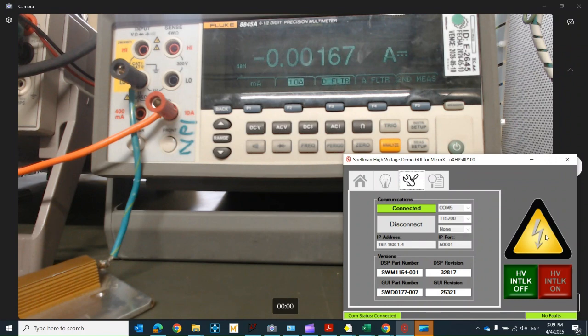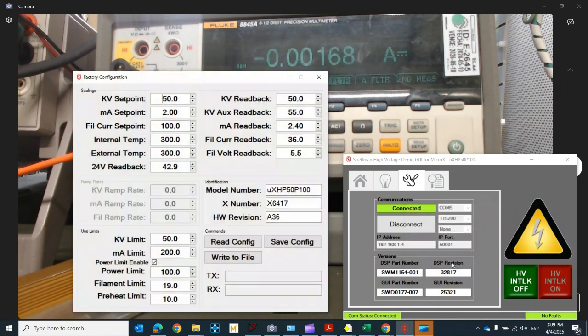Before proceeding with the computer interface test, we will also present a reminder of the access to the factory settings, which can be accessed by Alt plus double-click on the high voltage logo and entering the password. Once open, factory settings will appear. These contain information such as scaling factors for the GUI monitor signals, the model number and revision for the X6417, among other information, but the most important being the filament and preheat limits and the power limitation.